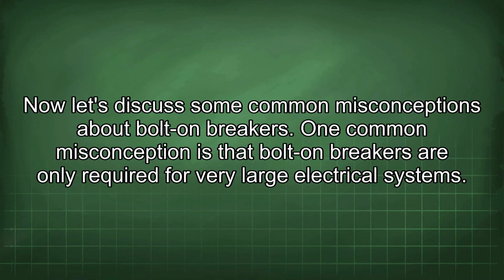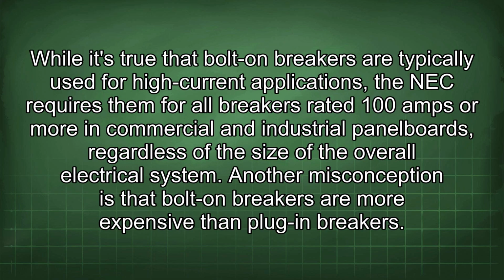Now let's discuss some common misconceptions about bolt-on breakers. One common misconception is that bolt-on breakers are only required for very large electrical systems. While it's true that bolt-on breakers are typically used for high current applications, the NEC requires them for all breakers rated 100 amps or more in commercial and industrial panel boards, regardless of the size of the overall electrical system.